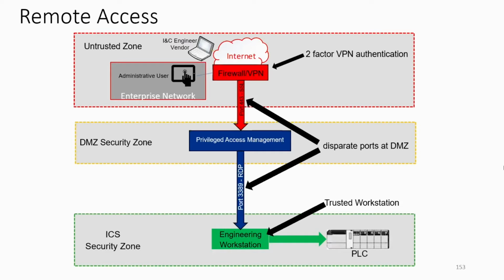They VPN'd into the system as designed and controlled it, using the HMI as designed to turn off the breakers, then bricked the UPS so operators couldn't bring the system back online. That happened because there was no two-factor authentication. That's a critical, must-have thing nowadays—if you have any remote access, you need multi-factor authentication at your VPN.